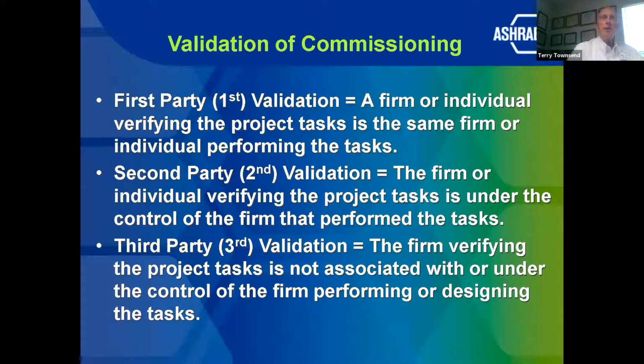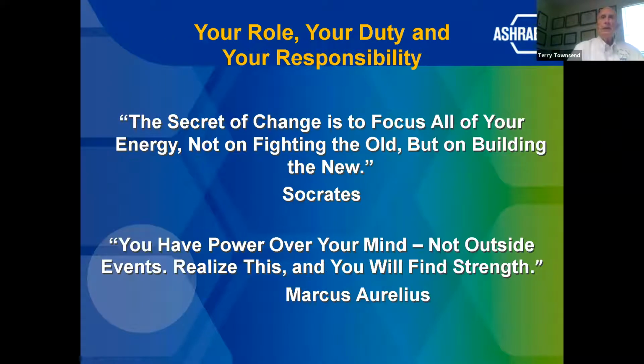Now, validation of commissioning. First party, this doesn't work, as the firm or individual verifying the project is the one that did the project. Second party is the firm or individual verifying the project is under the control of the firm that performed the task. That is why I am advocating, as many of the consultants know, with TAB contractors, I know that probably some of the best fiction that you have ever read are TAB reports, because they're being conducted for the mechanical contractor. You go out and you do your observation and inspection, and it's nowhere close. So that's why third party validation says that the firm that is verifying the project is not associated with or under the control of any firm performing it or designing it, but works totally for the owner. Works totally for the owner. So the secret of change is to focus all of your energy not on fighting the old, but on building the new.